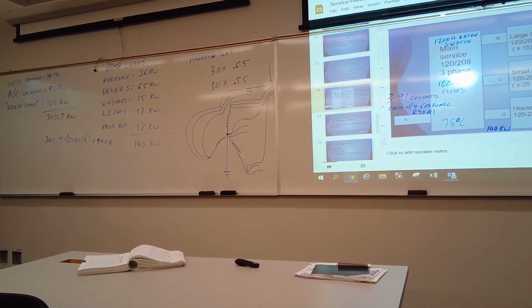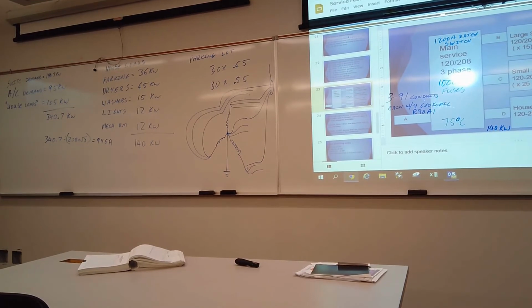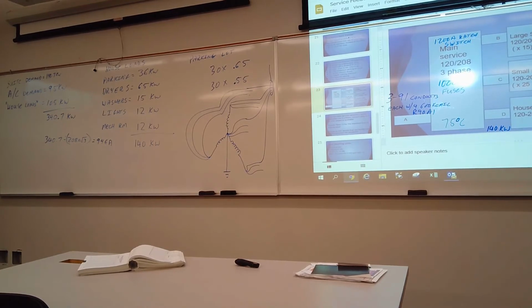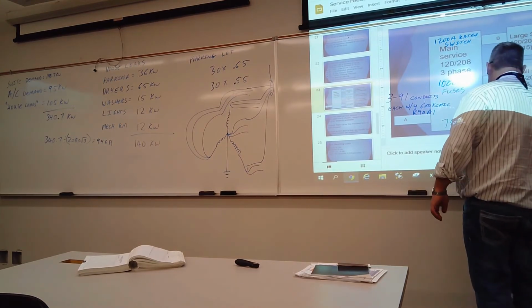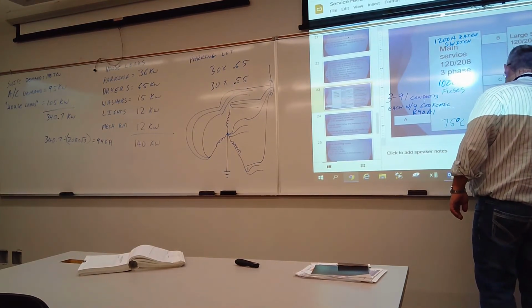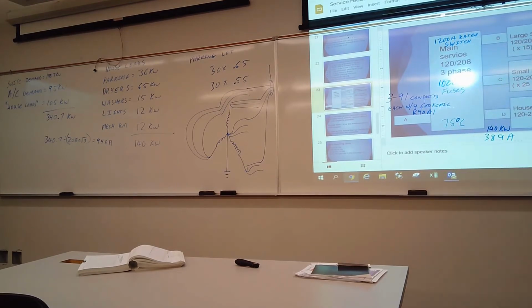140 divided by 208 times root 3, because you would run this as a three-phase. This would be a three-phase panel. So 140 divided by 360, 389. 389. So this is going to have a minimum of 389 amps. Okay. Sorry.